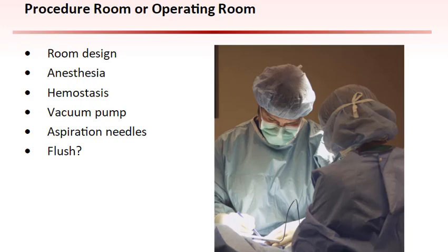Aspiration of follicular fluid requires the insertion of an aspiration needle into the Graafian follicles of the woman's ovaries and application of suction to draw the follicular fluid out of each follicle and deposit it into a tube for examination. The suction may be provided by a vacuum pump or by syringes, and the suction method must be available in the room at the time of the procedure.